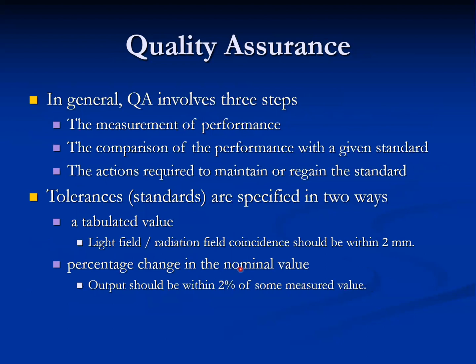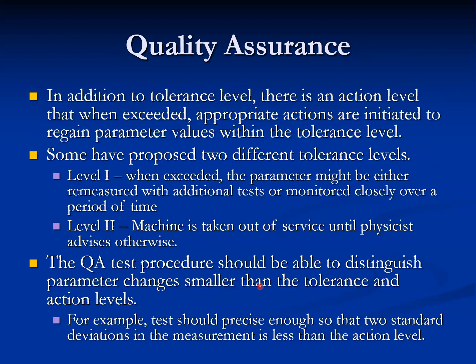Quality assurance in general involves three steps: the measurement of performance, the comparison of performance with a given standard, and the action required to maintain or regain the standard. Tolerances are specified in two ways — tabulated values, for example, light field and radiation field coincidence should be within 2 mm, and output should be within 2% of the nominal value. Beyond these tolerance levels, there is an action level that, when exceeded, initiates appropriate action to regain the parameter value within tolerance.